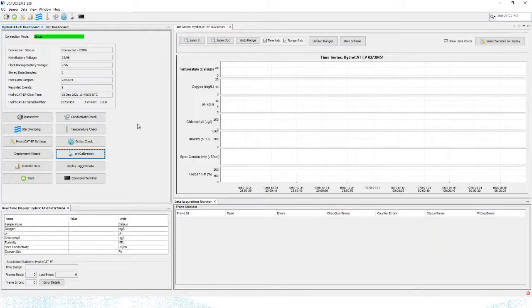That's a little cap that you put onto your HCO optical sensor that's going to output some expected data. Note that this optics check is temperature dependent, so try to do it at around 22 degrees Celsius if you can. That's how you make sure your sensor or instrument is ready to go, your sensors are responding as expected, and your HydroCAT EP is ready for deployment.